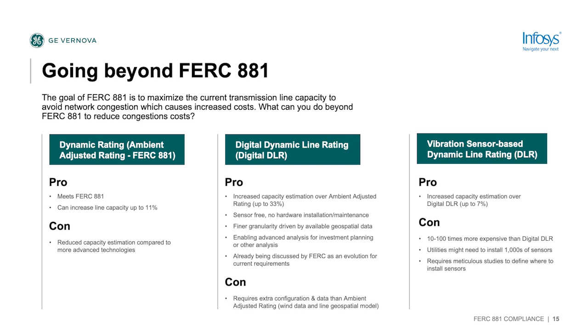For minimum compliance, the one on the left, our ambient adjusted ratings, is our dynamic rating application. It meets the FERC 881 requirement. It does increase the line capacity approximately 11%, but it doesn't increase the capacity compared to other solutions. Our digital dynamic line rating gives you ambient adjusted rating increases of up to 33%. It's hardware free, low installation, low maintenance cost, and basically a single software installation can unlock capacity across your entire footprint.